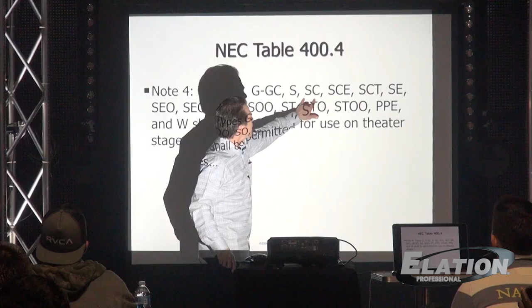Quickly, the whole point of this right here is that this is the National Electrical Code. It says for theater stages. Now it also pertains to any performance type areas, anytime you have portable equipment. And this pertains specifically to feeder cable. It says we can use all these different types of cables. Cables have types, and it's stamped on the cable. And the type that we use most often for our shows is type SC. This type right here, that's what we call entertainment cable.